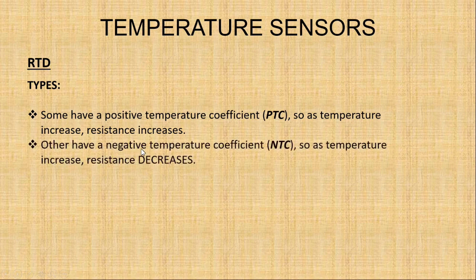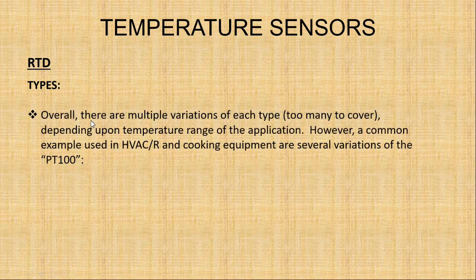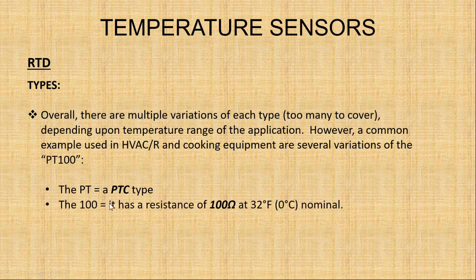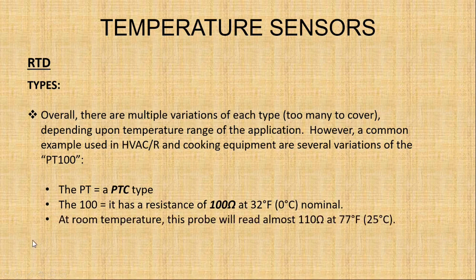Some RTDs have a negative temperature coefficient, so as temperature increases, resistance decreases. Overall, there are multiple variations of each type, depending upon the temperature range and its application. However, a common example used in HVACR and cooking equipment are several variations of the PT100. Now, the PT stands for its positive temperature coefficient type, and the 100 is that it has a resistance of 100 ohms at 32 degrees Fahrenheit nominal. At room temperature, this particular probe so happens to read almost 110 ohms, and room temperature is 77 degrees typically.